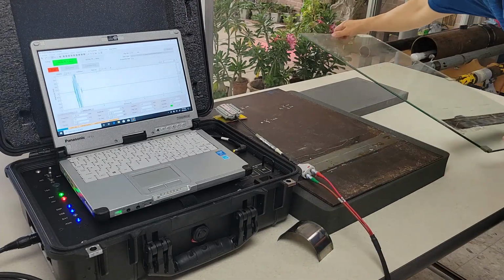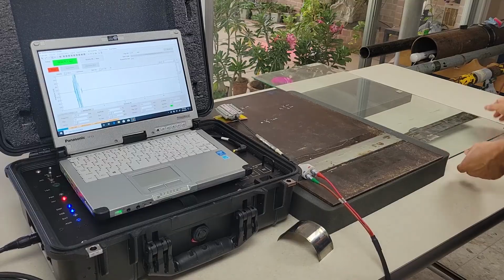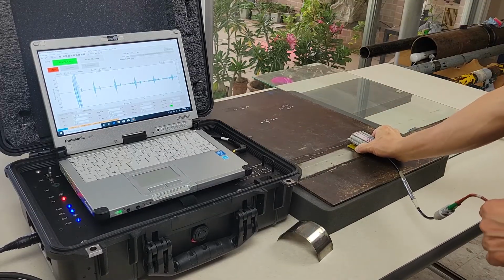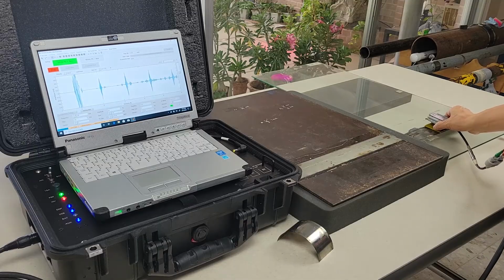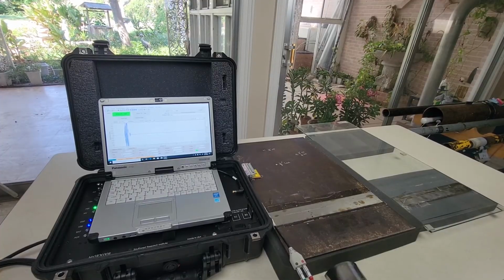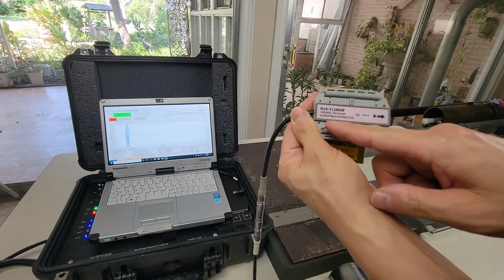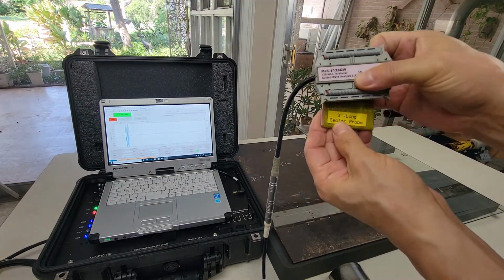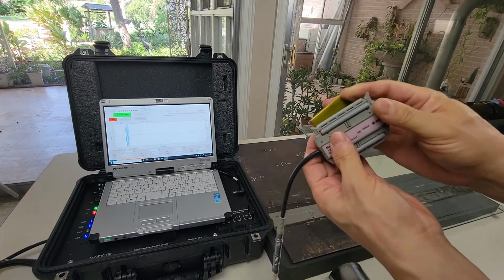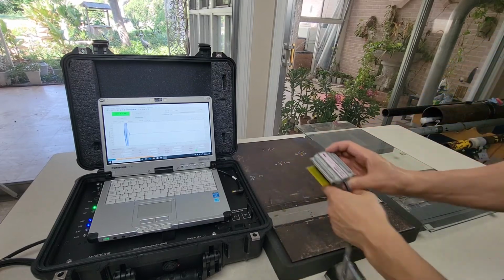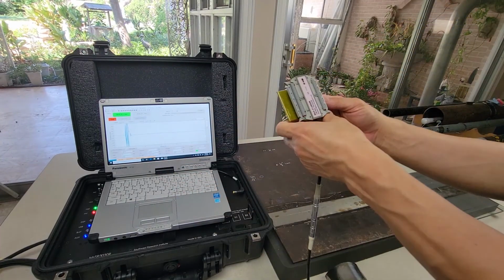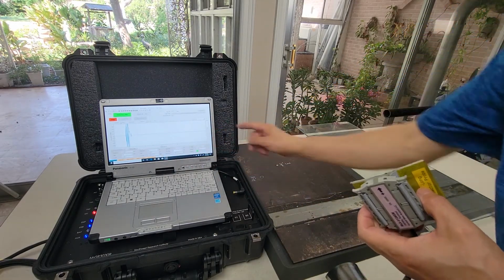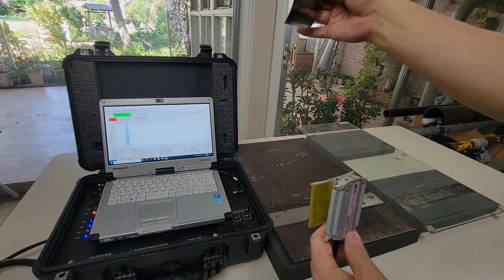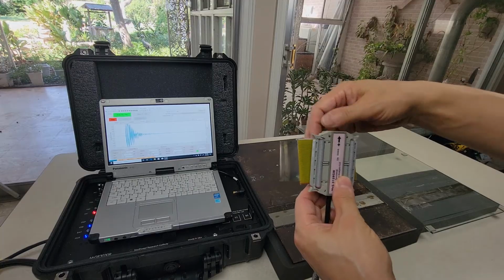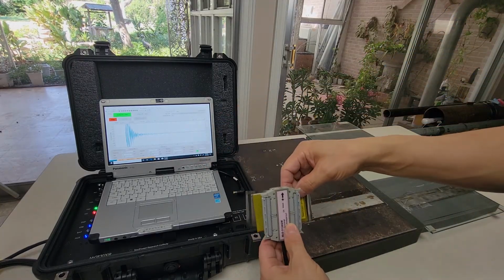This is our live demonstration of wave propagation on both steel and glass plates using the guided wave testing (GWT) system with a magnetostrictive sensor or MSS probe. Here we are working with an MSS probe specifically designed for high sensitivity inspection of pipelines or plates of pressure vessels and tanks. This probe generates a magnetic field directly beneath it. And when there is no ferromagnetic material attached, we only observe the initial pulse in the live signal. However, when we attach a ferromagnetic strip, mechanical vibrations are created within the strip as shown in the live data.